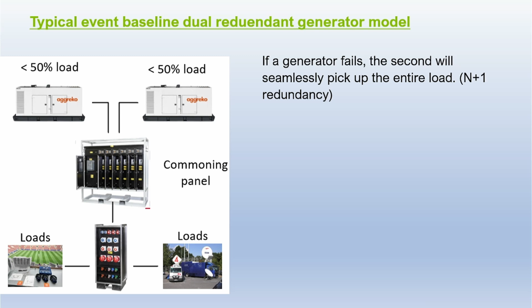So the most common and typical way we've powered events for years is to have a dual redundant generator model. You have two generators running in parallel, powering the load, so that if one falls over, the other takes the load seamlessly and everything carries on, which is great. But the challenge is they don't run efficiently, because if you split the load between 2 generators with the aim of one taking the full load, they both by default operate at well under 50%.